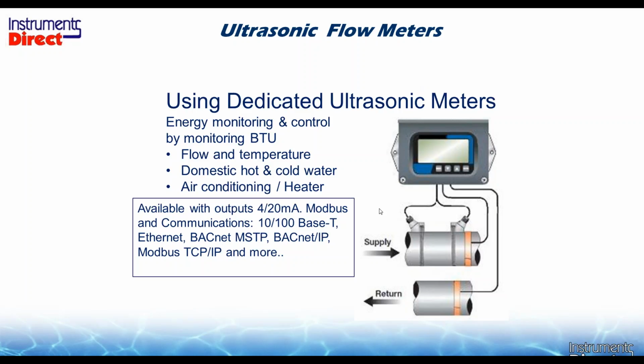And the key here is to tie it in to the university or the building's own building diagnostic system. That's where things have evolved, is the communication. So we can use their own building automation systems to log and compile the data. If they have something that takes 4 to 20 or Modbus or Ethernet, and some of the newer facilities will have BACnet MSTP or BACnet IP, Modbus or TCP/IP, you plug in an Ethernet cable, basically an Ethernet jack, that's just plug and play and talks to the systems to dump the data on the building automation system.